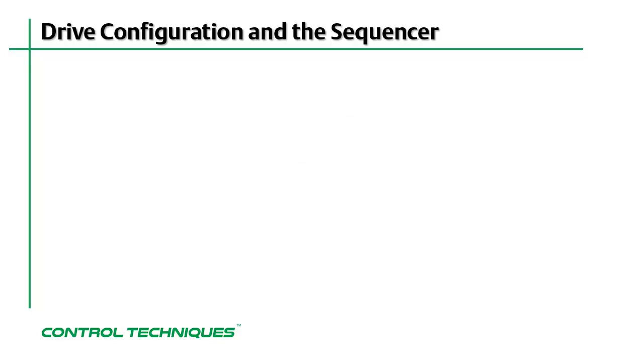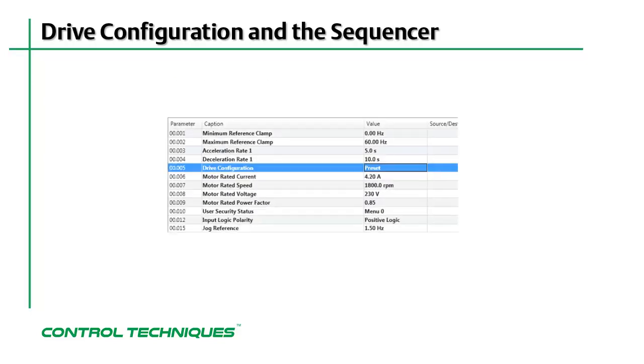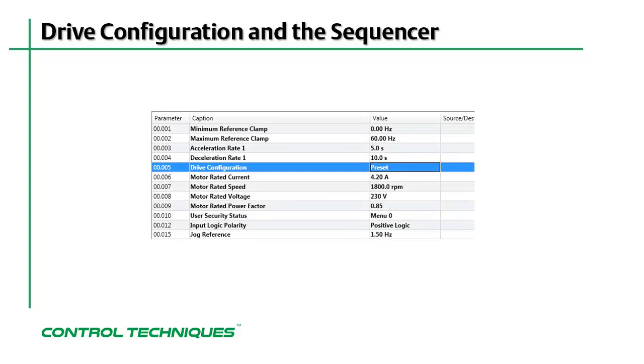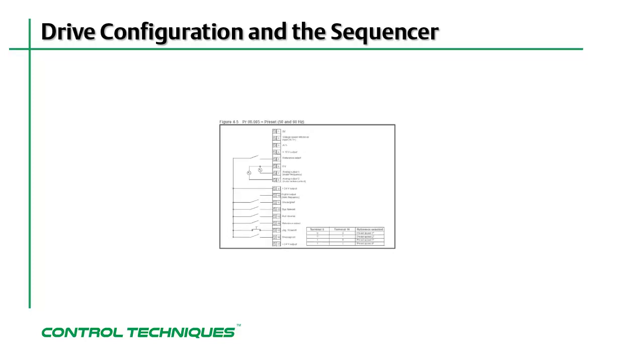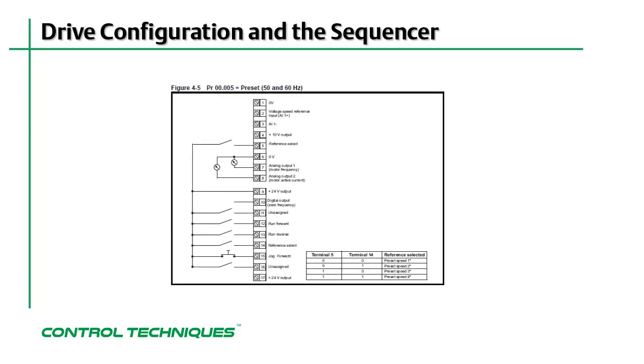I'll now change the setting for this parameter to preset. In preset mode, the drive will get its speed reference from one of four user programmable preset speeds. Here is the diagram for how the sequencer functions have changed to accommodate this drive configuration.